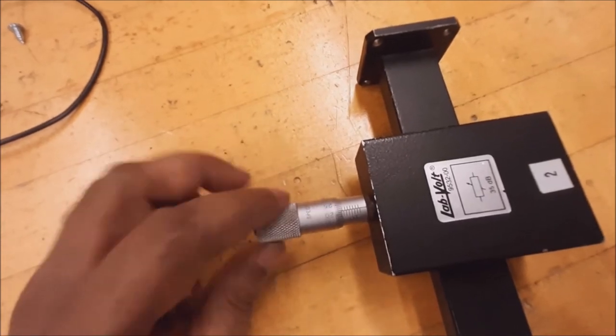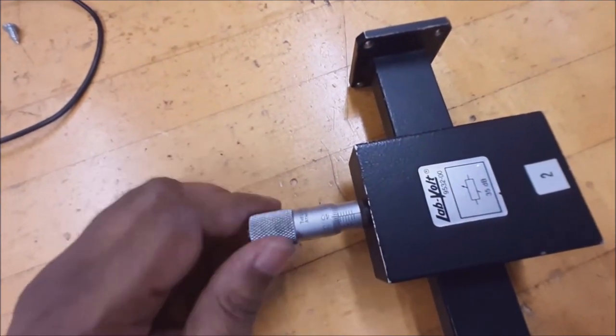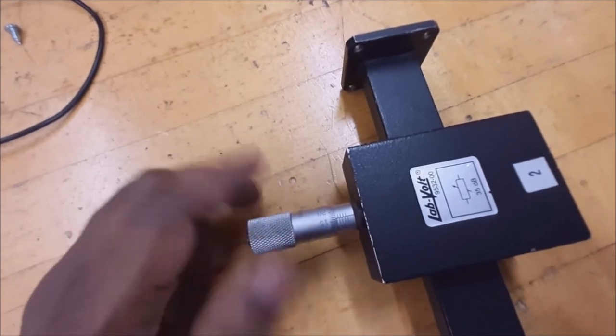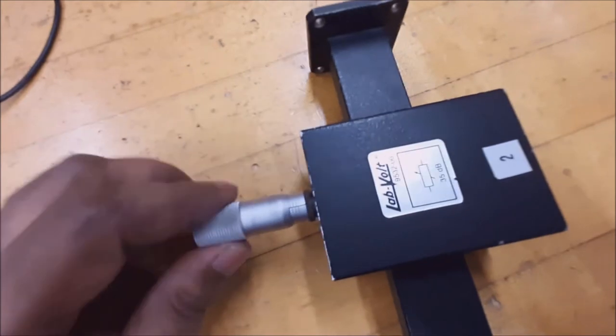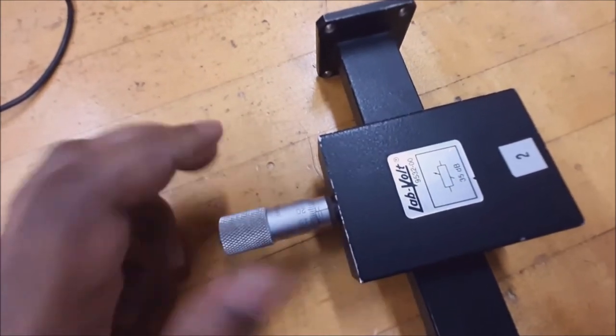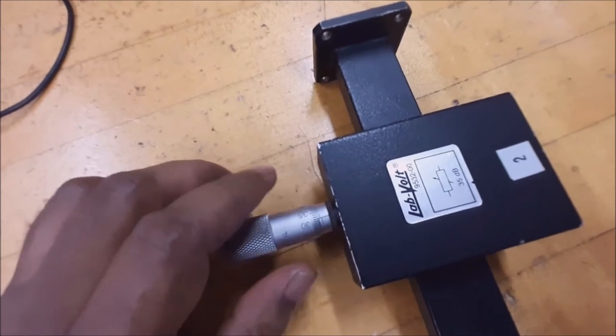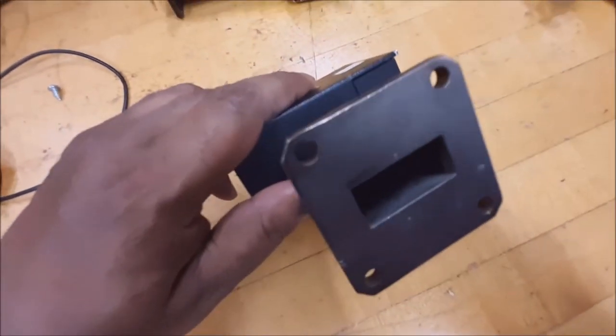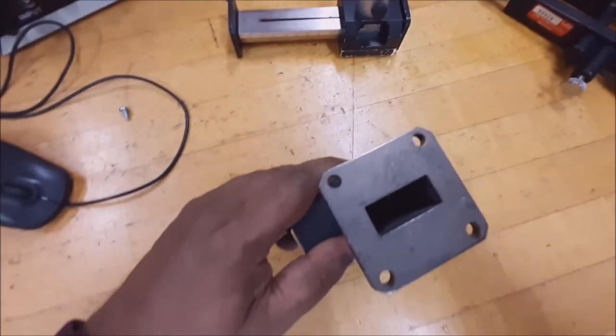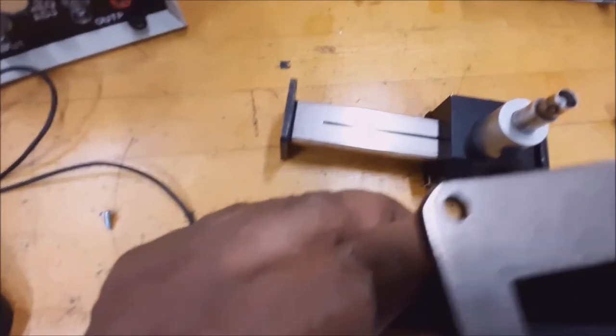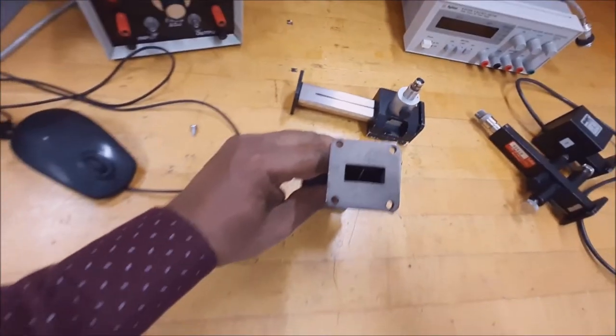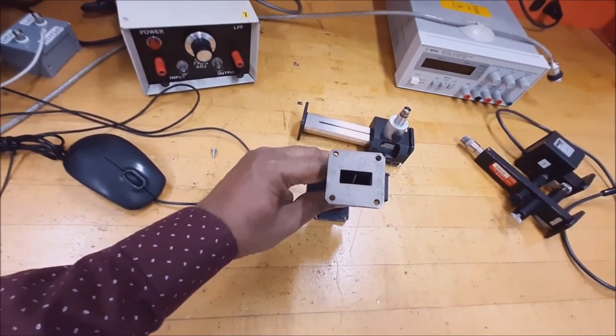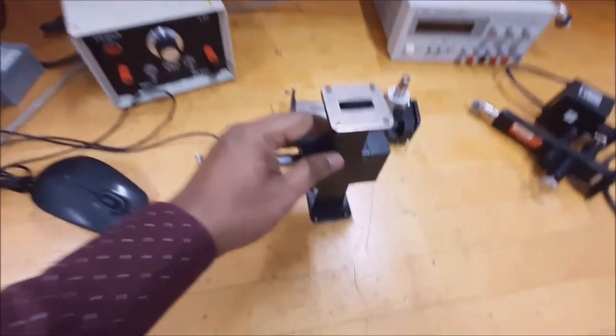So if you set 11 on the variable attenuator, no signal can pass through this, because of the blade of the attenuator. You can see the blade inside the hole here, the blade is at the middle of the hole. So if the blade is at the middle, no signal can pass through this. The signal coming at the input will be completely attenuated, so the output signal will be zero.